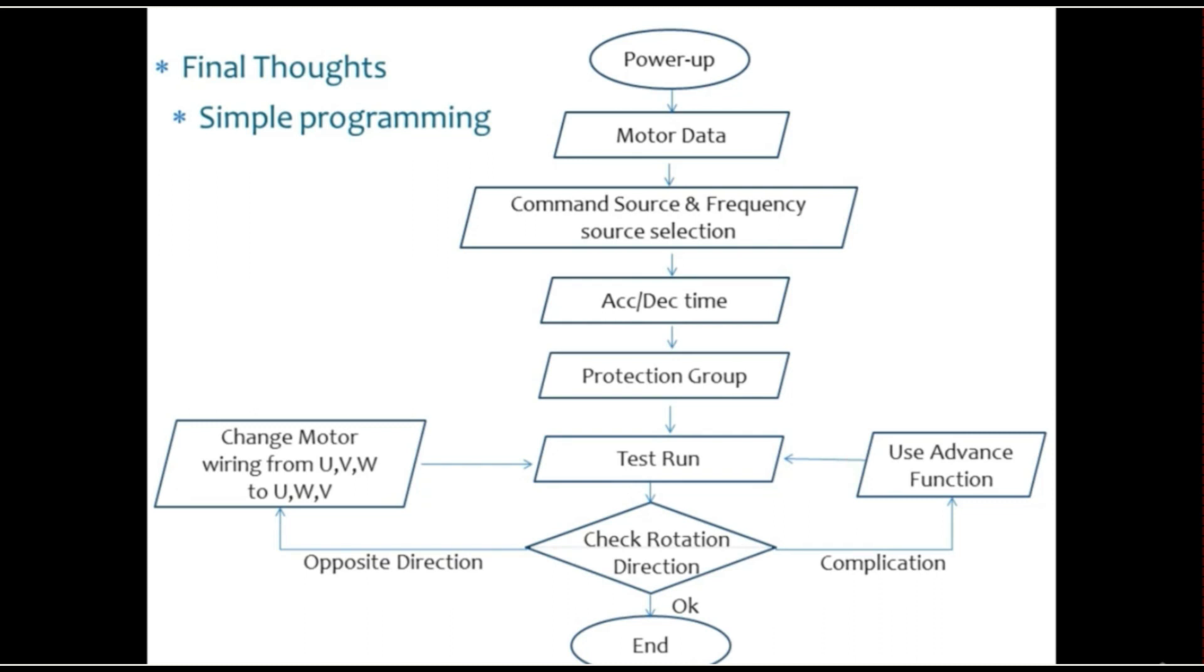Finally, after every programming, do not forget to enable protection features such as input and output phase protection as discussed in section 8, and also enable overload protection. Test the motor in running condition thoroughly, and then it's all done.